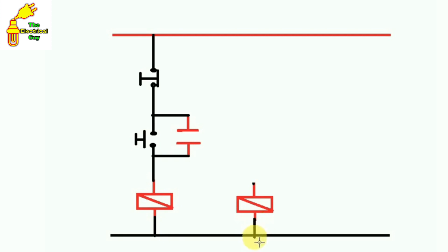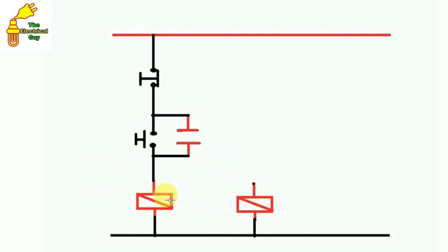In this condition, how to do the connection? Listen carefully. First, connect this contactor with the neutral supply. The first condition is: when this contactor is turned on, the other must not turn on, and vice versa. This is known as interlocking — both contactors are interlocked with each other. To interlock these, we break this circuit here and we are going to use NC contacts.